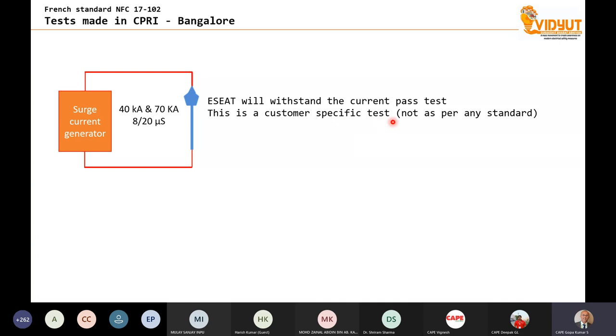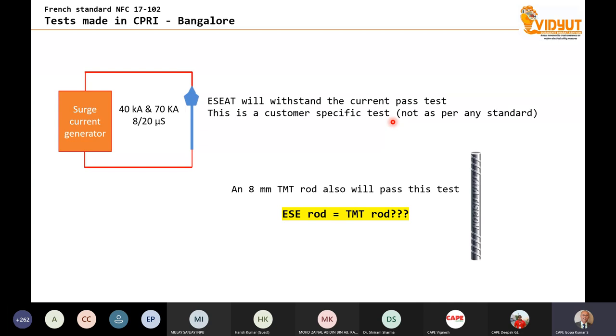Customer-specific test. Instead of this ESE rod, if I have an iron rod and I go to CPRI and say, look, I have an iron rod, can you test it for 40 kiloampere? Of course, if I pay the money, they will test, because this is a customer-specific requirement. Now, this same test which is conducted in CPRI can also be done with an 8 millimeter thick TMT rod. All of you know what a TMT rod is. TMT rod is the iron rod which is used in construction steel. The same test which is conducted for the ESE in the CPRI can be conducted on an 8 millimeter TMT rod, and the TMT rod will also pass the test. Does it mean that the ESE rod is equal to a TMT rod?